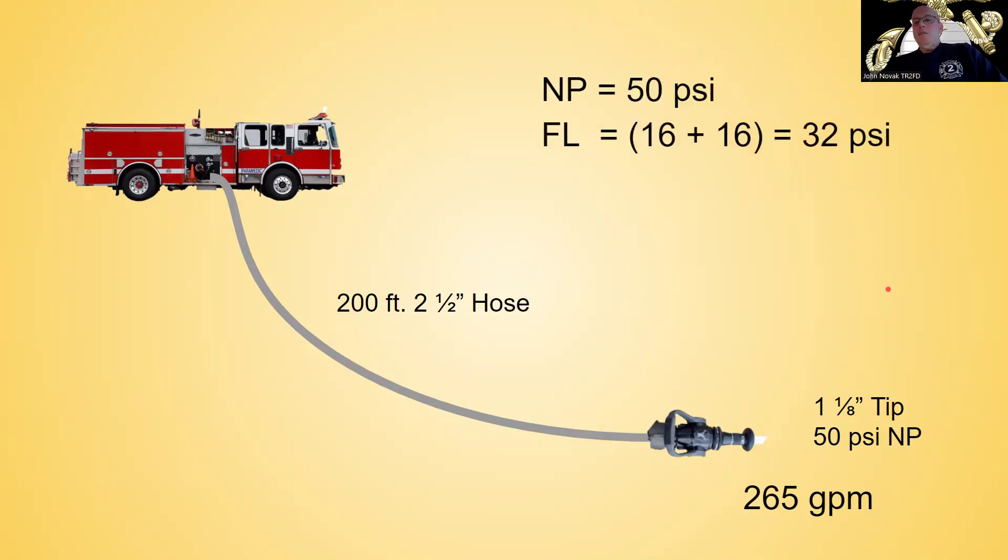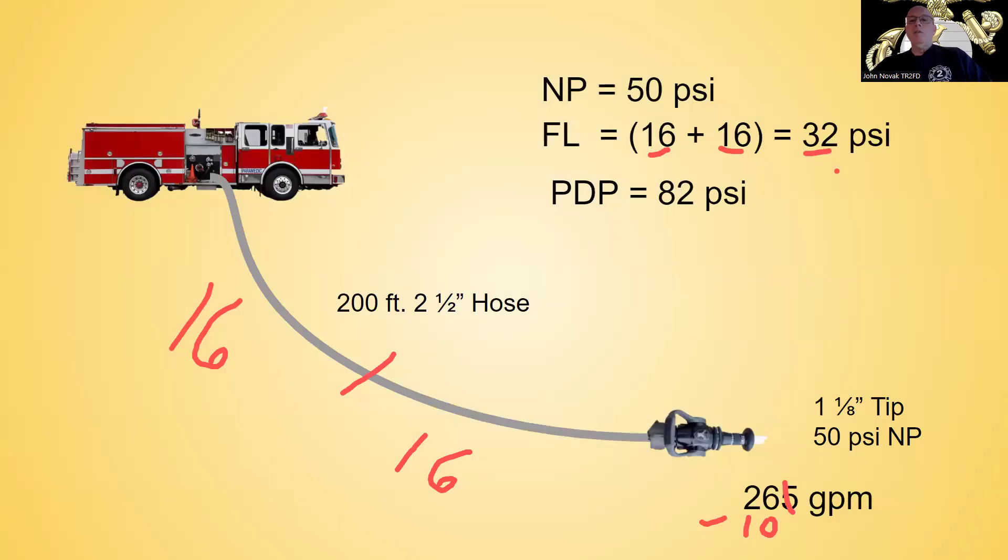So my nozzle pressure is 50. So going by my drop 10 method, I'm going to take 265. And we're going to get rid of this last number, and we're going to subtract 10. That leaves me with 16. So there's two lengths, so there's 100 feet here, so that's 16 psi loss here, 16 psi loss here. 16 plus 16 equals 32. So my friction loss is going to be 32. I add in my 50 pounds nozzle pressure, and I end up with my pump discharge pressure, 82 psi.